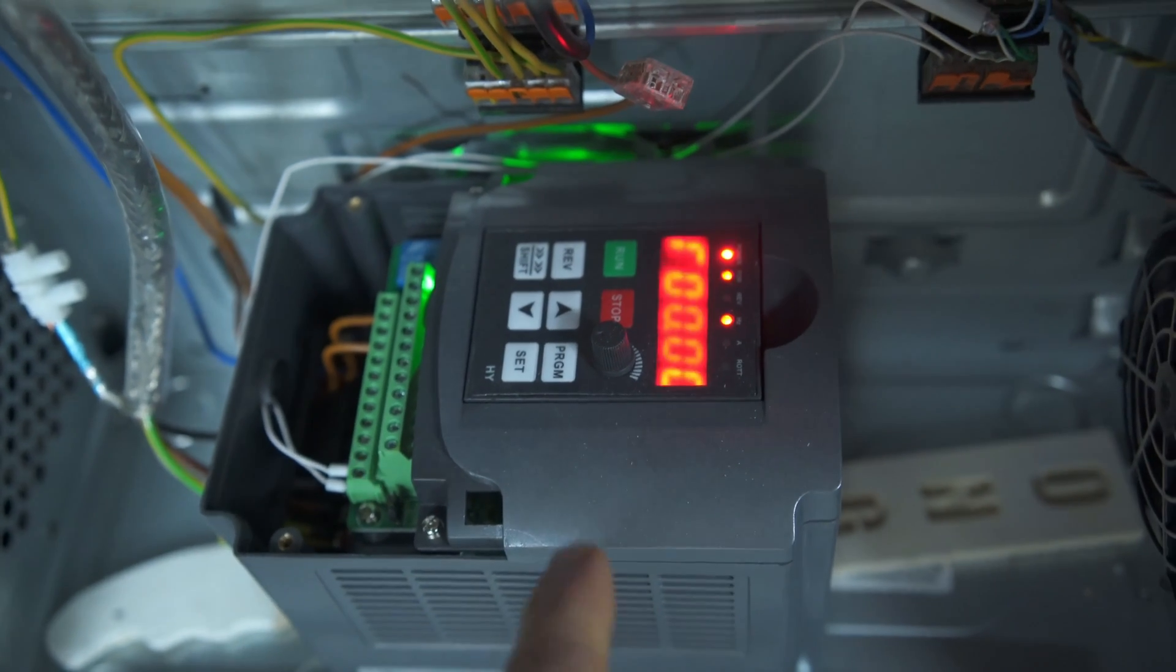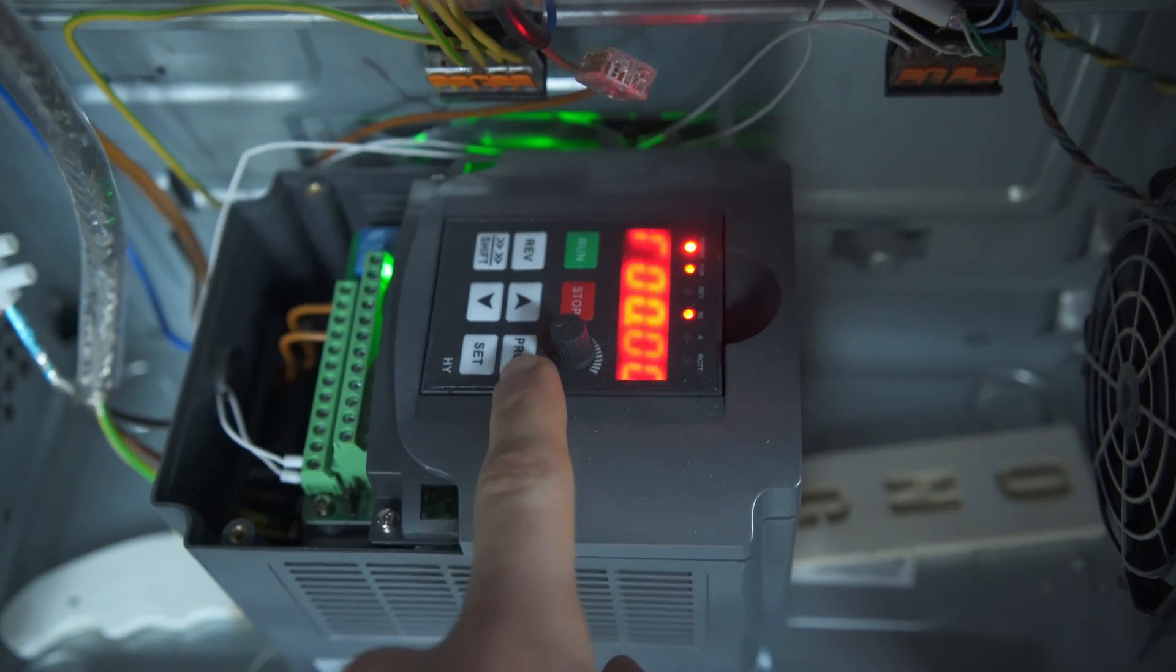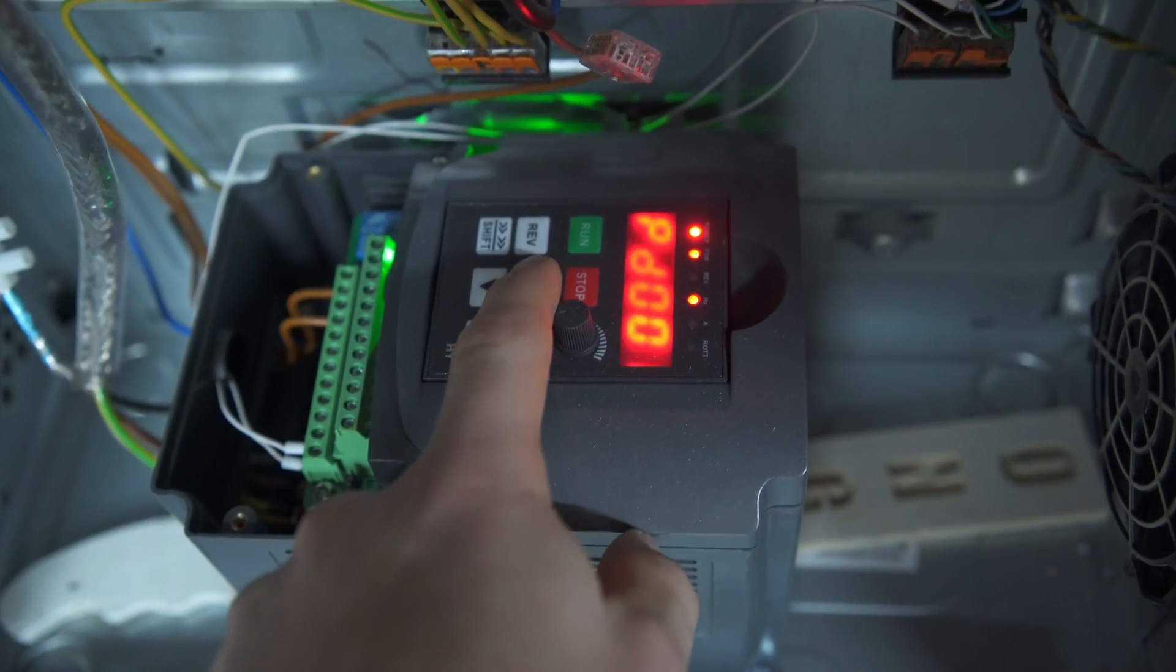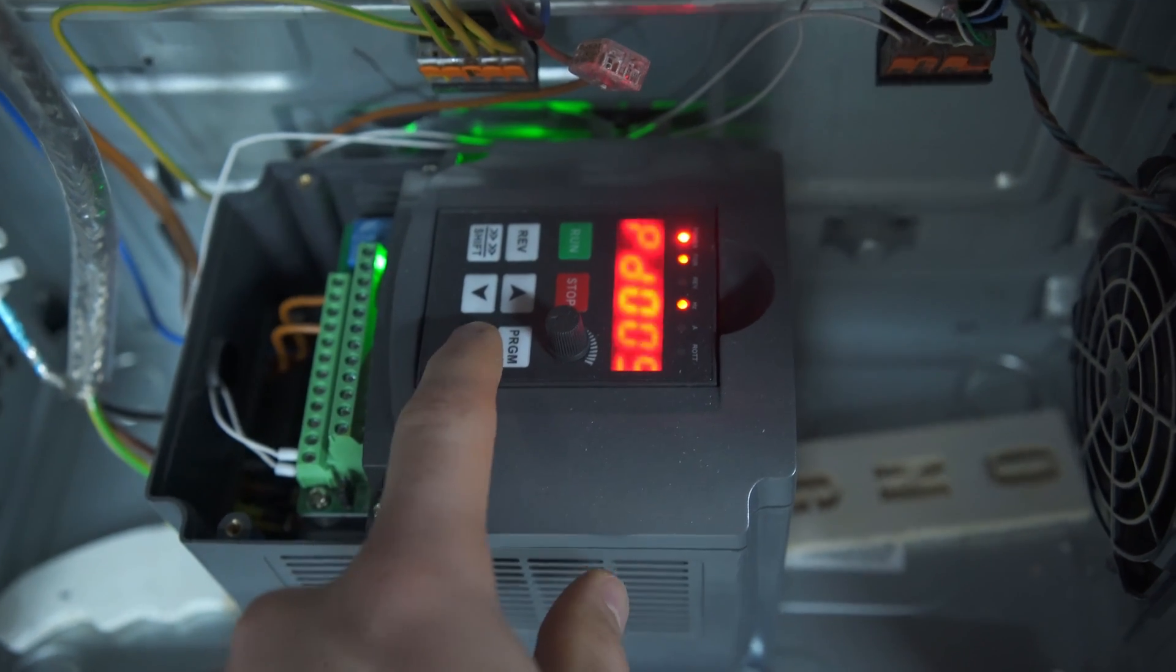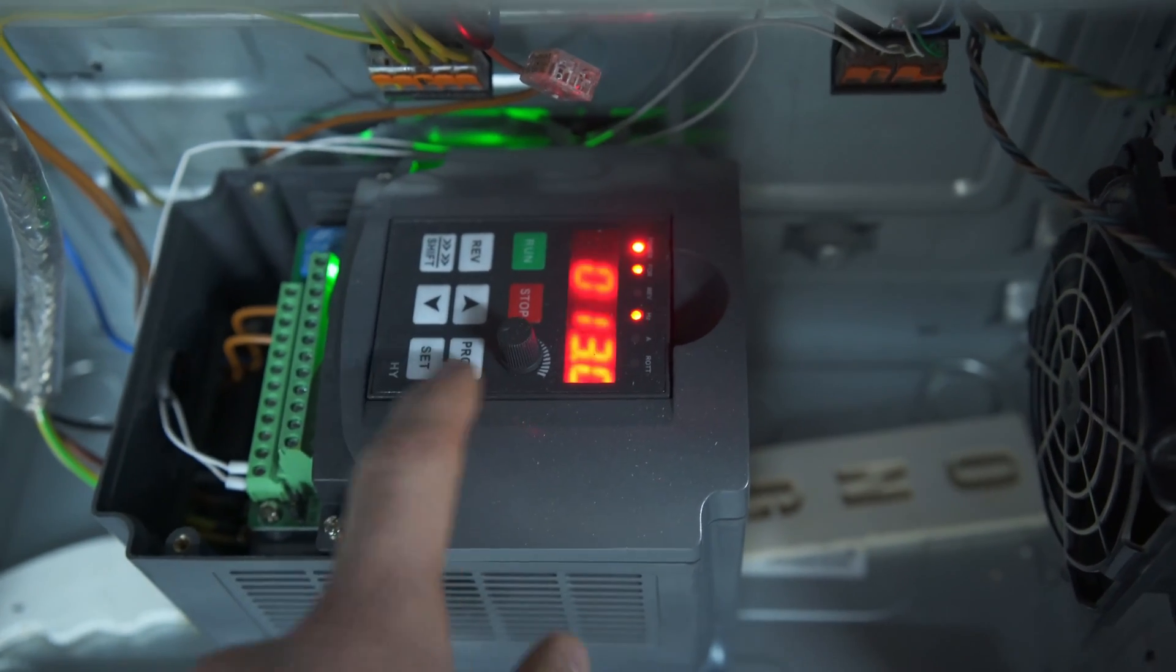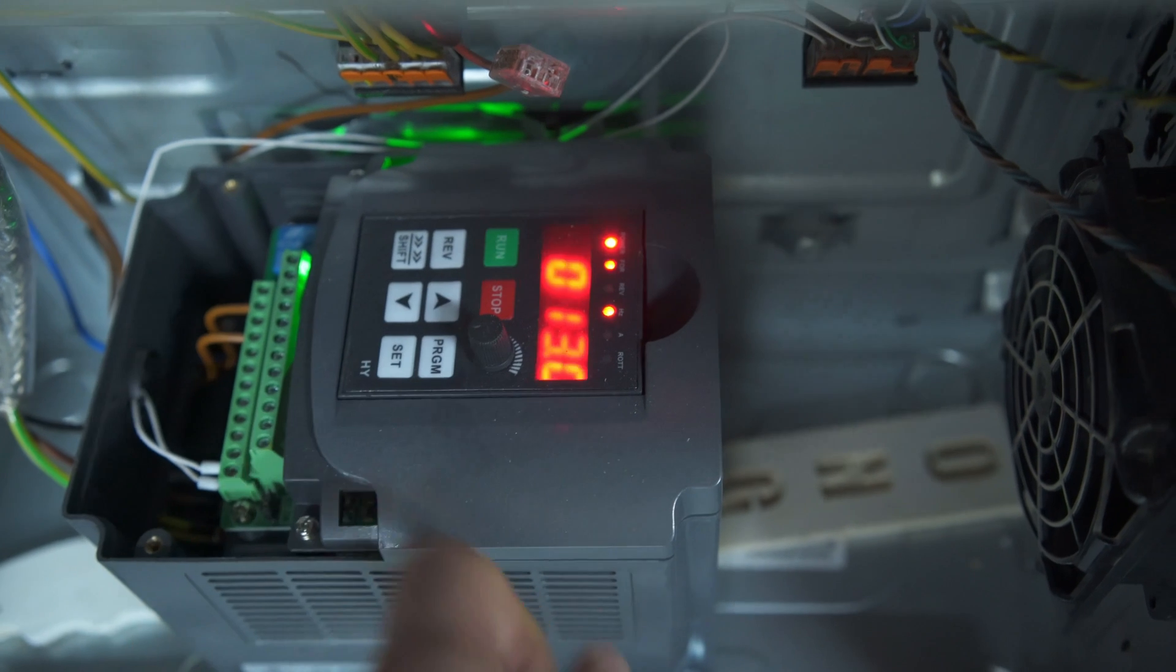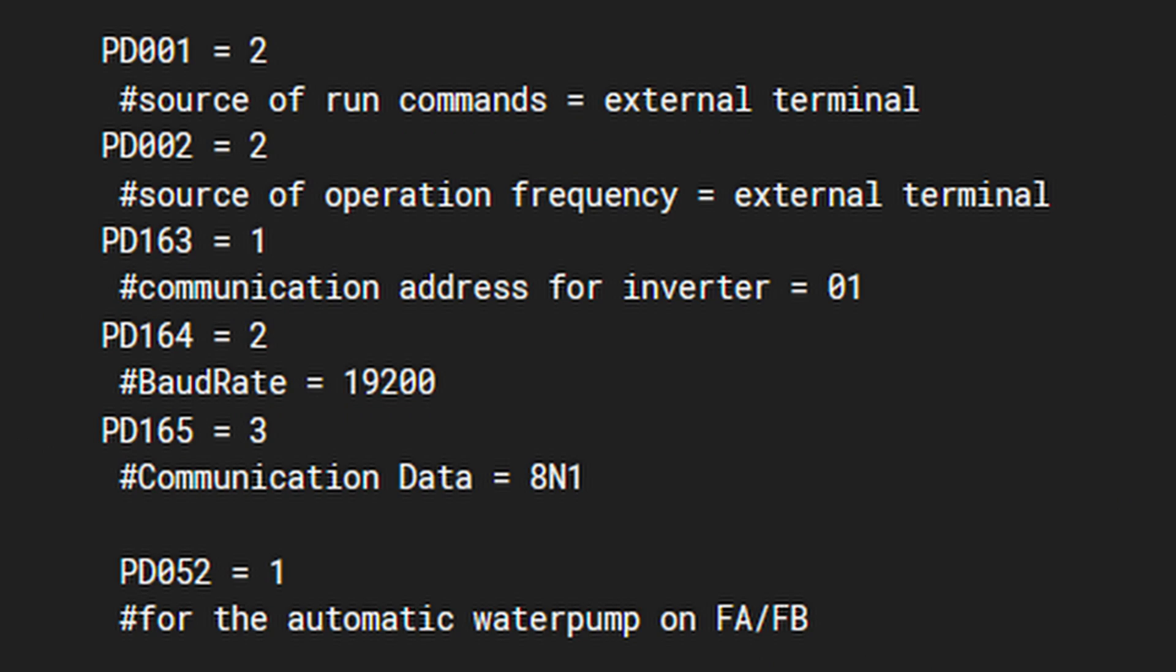We also need to do some changes to the VFD software. To program it press program. With the arrow keys switch to the parameter you want to change. Press set. Then change the parameter. Press set again and you are done. These are the parameters I had to change to control the VFD via Modbus.